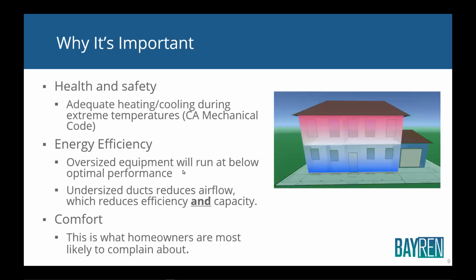So why is this all important? Why is it important to do load calcs? A lot of people don't realize this, but it really is a health and safety issue. If you look at the statistics of how many people die when there are heat waves and when power goes out and things like that. And so properly sizing equipment, making it work, is a health and safety issue, okay? Energy efficiency is what makes our grid more stable and prevents a lot of those blackouts and brownouts and things like that. Oversized equipment will not only use more electricity, it's running at below optimal performance, all right? I'll show you some things. There's a lot of things wrong with oversized equipment.